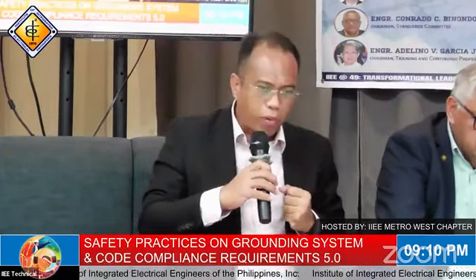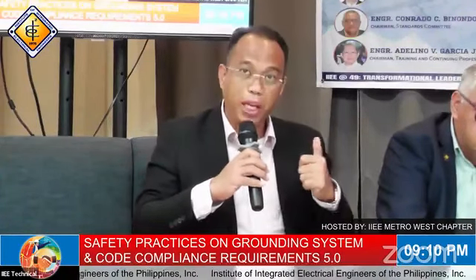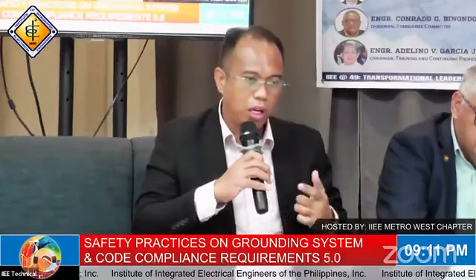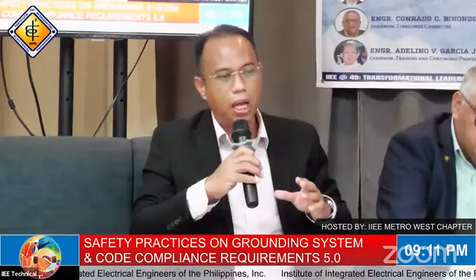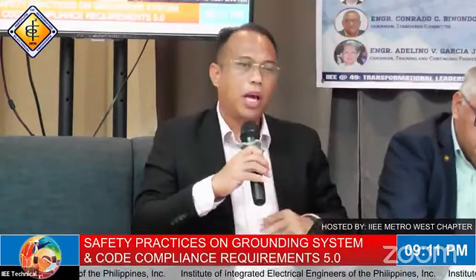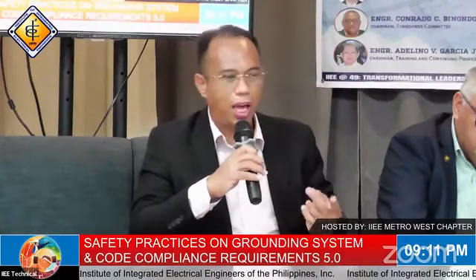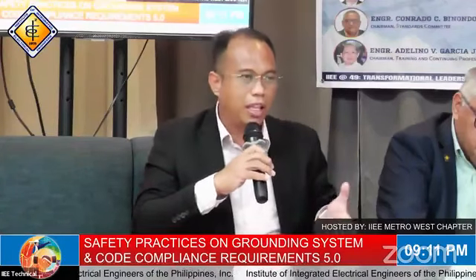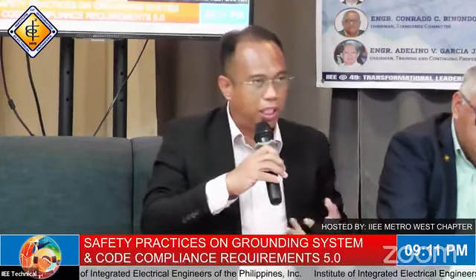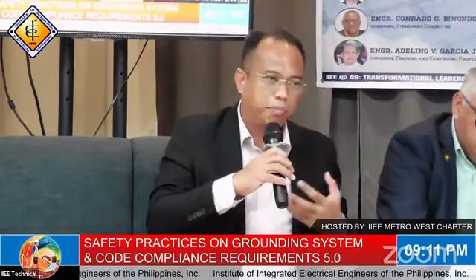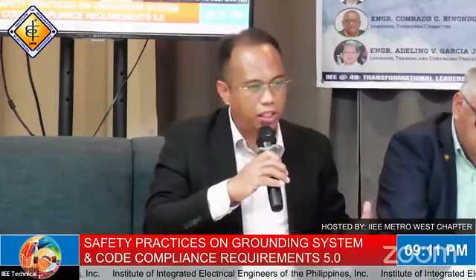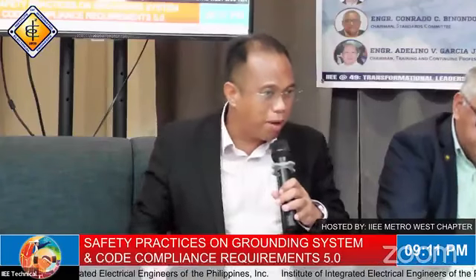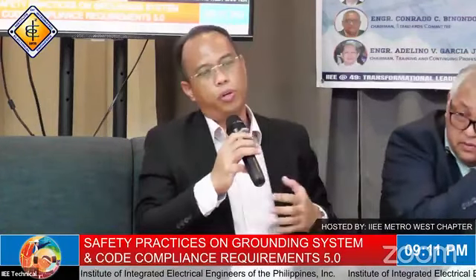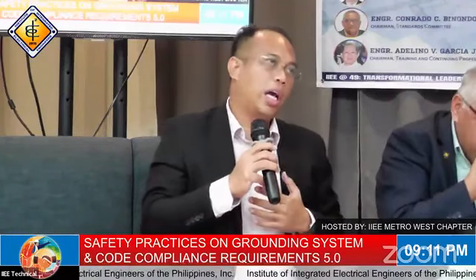There are a lot of items being considered right now. One is the duration of our ATS system, there are specific number of seconds for transfer. The other one is even if everything gets burned, wag lang yung fire pump. Kaya nga yung type of circuit breaker natin is intended na kahit magkaroon ng fault, aandar pa rin siya. And yung backup system natin, nabanggit din yung fire alarm, so there must be a backup supply power for our fire alarm system, kasi ang importante doon is para makadating agad yung first responders natin like the firemen.